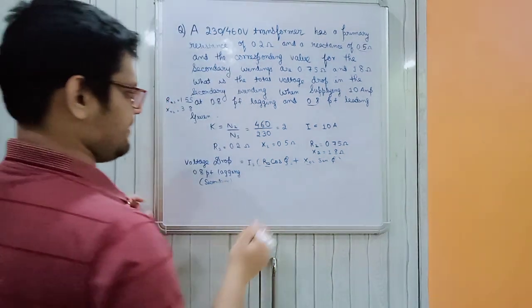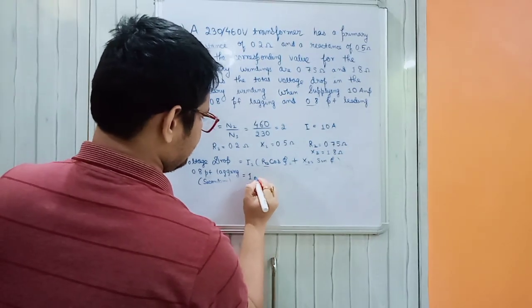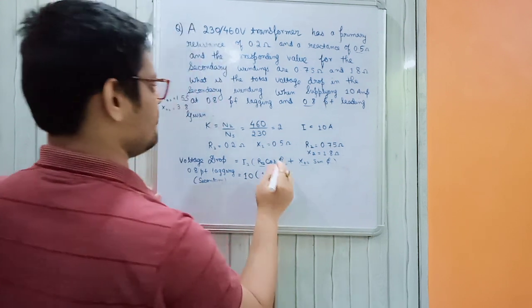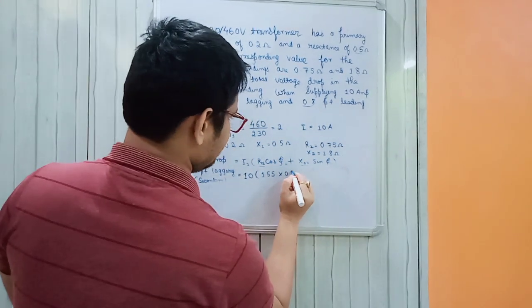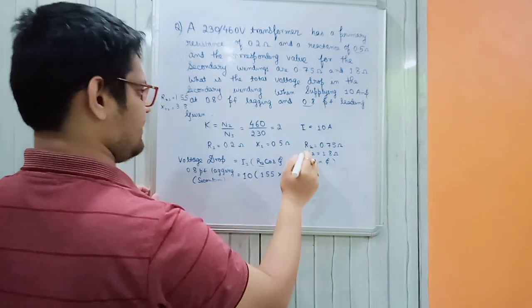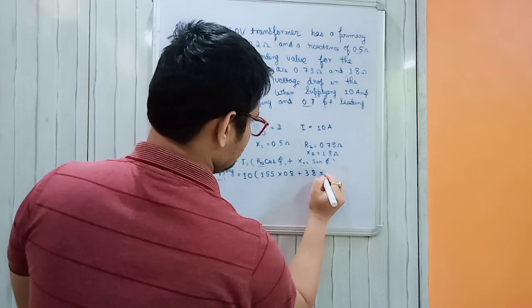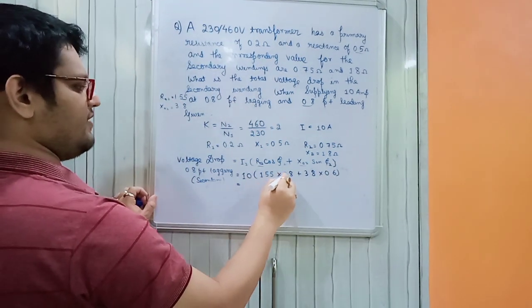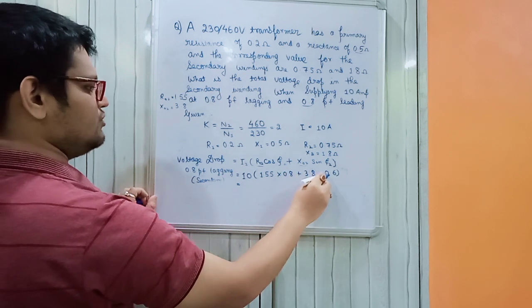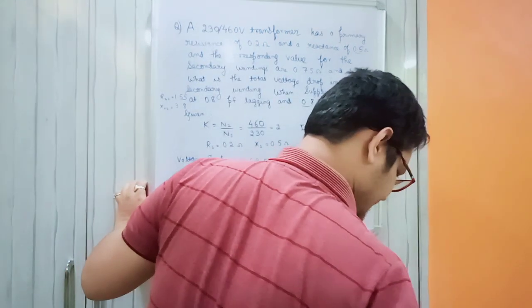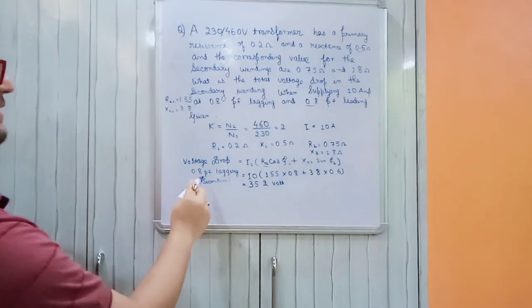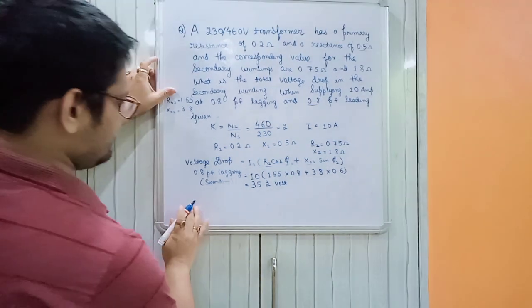For 0.8 power factor lagging, voltage drop = I2 × (R02 × cos φ₂ + X02 × sin φ₂) = 10 × (1.55 × 0.8 + 3.8 × 0.6). Calculating: 10 × (1.24 + 2.28) gives the voltage drop at 0.8 power factor lagging.